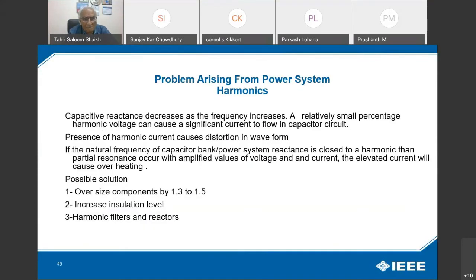Now I come to the different solutions. The capacitive reactance decreases as the frequency increases. A relatively small percentage harmonic voltage can cause a significant current to flow in capacitor circuits. Presence of harmonic current causes distortion in the waveform. If the natural frequency of a capacitor bank power system reactance is close to a harmonic, then partial resonance occurs with amplified values of voltage and current. The elevated current will cause overheating. Possible solution, maybe one of the easiest, is to oversize the component by 1.3 to 1.5, increase the insulation level, and third would be harmonic filters and reactors, which is the costly affair.